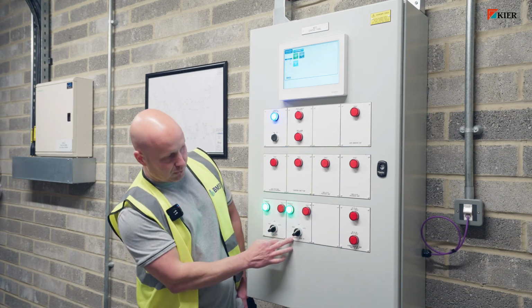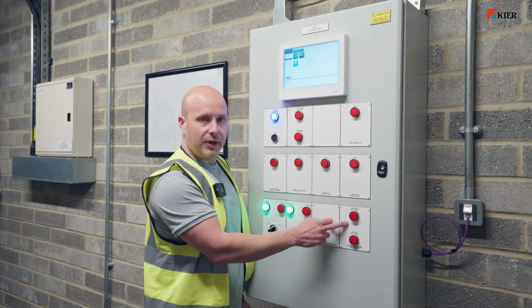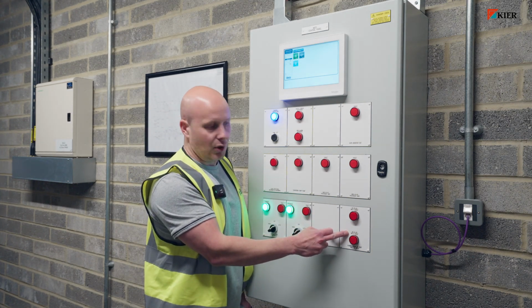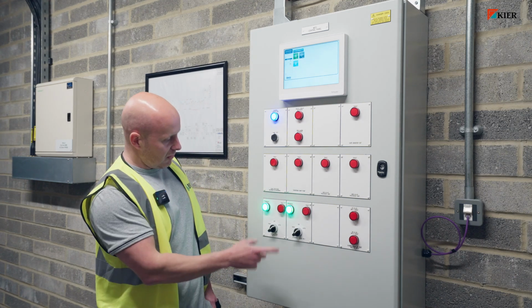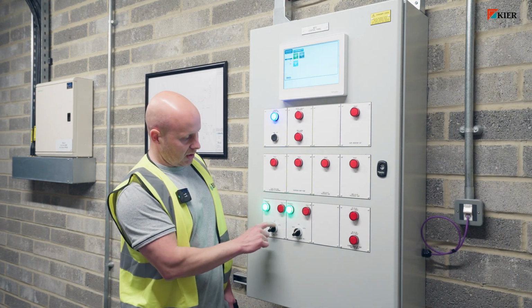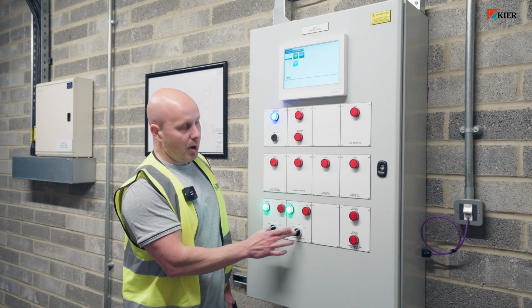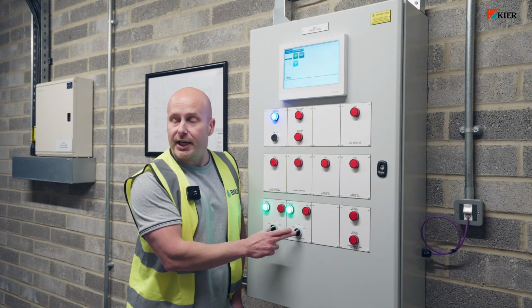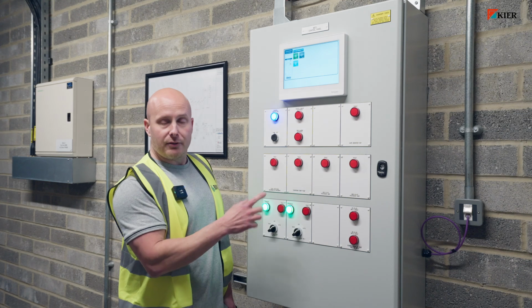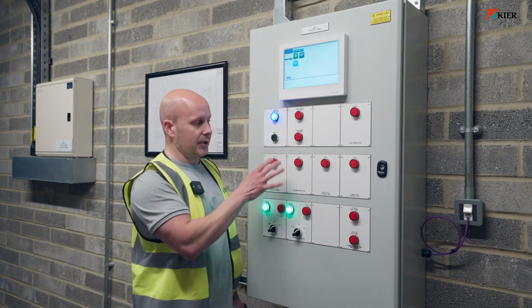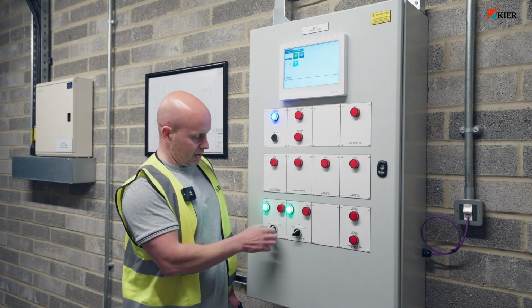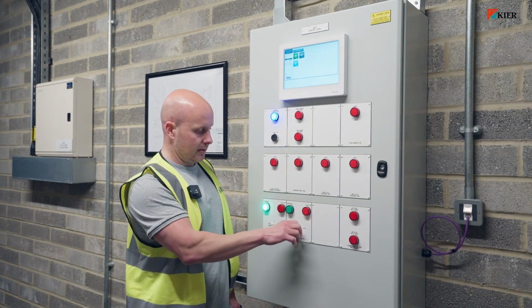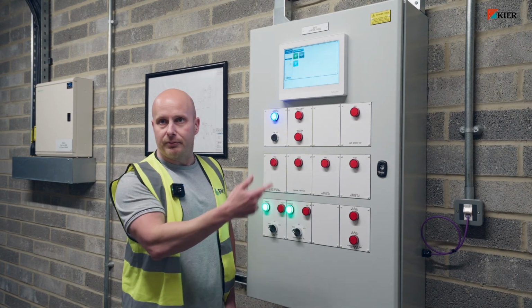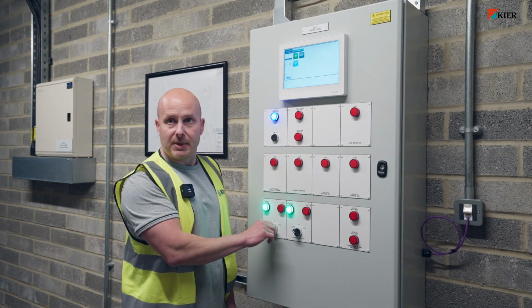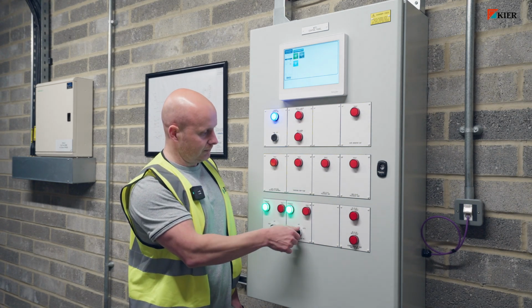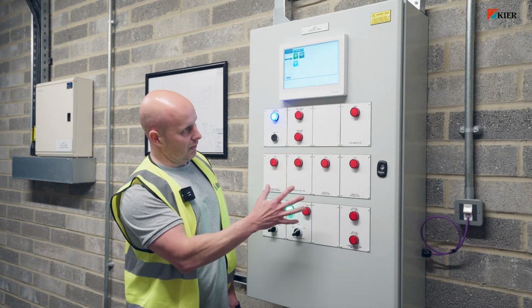We have a switch here for the overdoor heaters, and we have some faults for the air conditioning units for the comms rooms. With regards to these switches, the system's currently set into auto. However, the system is set to run 24/7 anyway. If for whatever reason the controller did fail inside this panel, what you can do to get these units running, you can switch them over to hand, and they'll run independently of the controller inside, but they should always be in auto. Okay, and that's the basic control of the front of the panel.